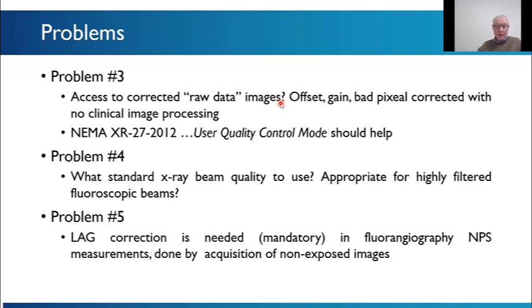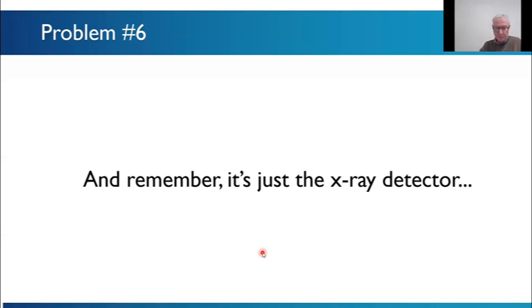So yeah, a big problem. We can't do this on most systems at the moment. What X-ray beam should you use? And then do you need to do lag correction? This is only really important if you want to measure the DQE. So, and remember, it's just the X-ray detector. So it's not image quality as such. It's an important aspect of image quality, and it sets the noise and the sharpness to some extent in the image along with the selected dose rate, but it's just a detector.